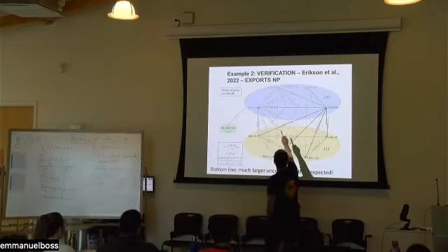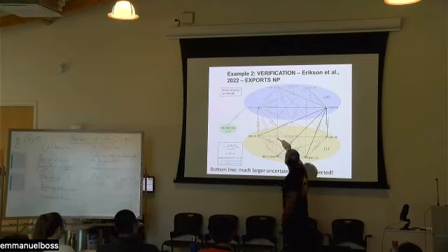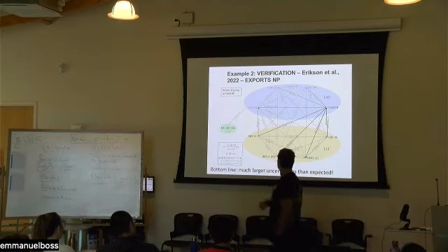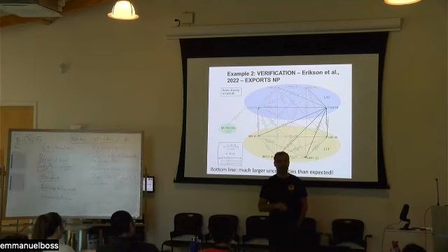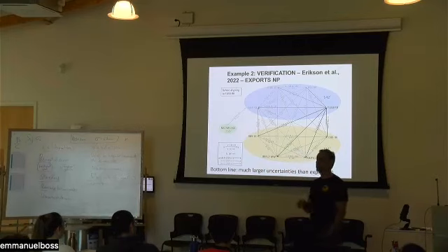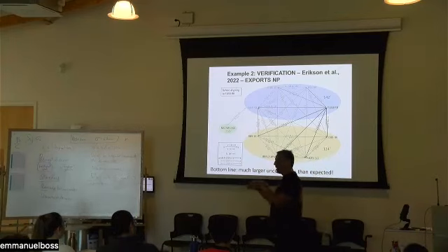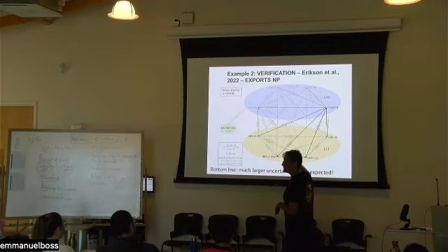When you have a slope of 0.95, you'd say, not too bad. And when you have a slope of 1.87, you say, wow, 87% difference in the slope. And here we have 1.2 and 0.9, 0.94, 1.3, 1.4, 2.44, two of the same sensor exactly, two FLBBs, both coming from the same lot, constructed by the same manufacturer. But how close were they? They were close enough. You did not expect those types of differences.